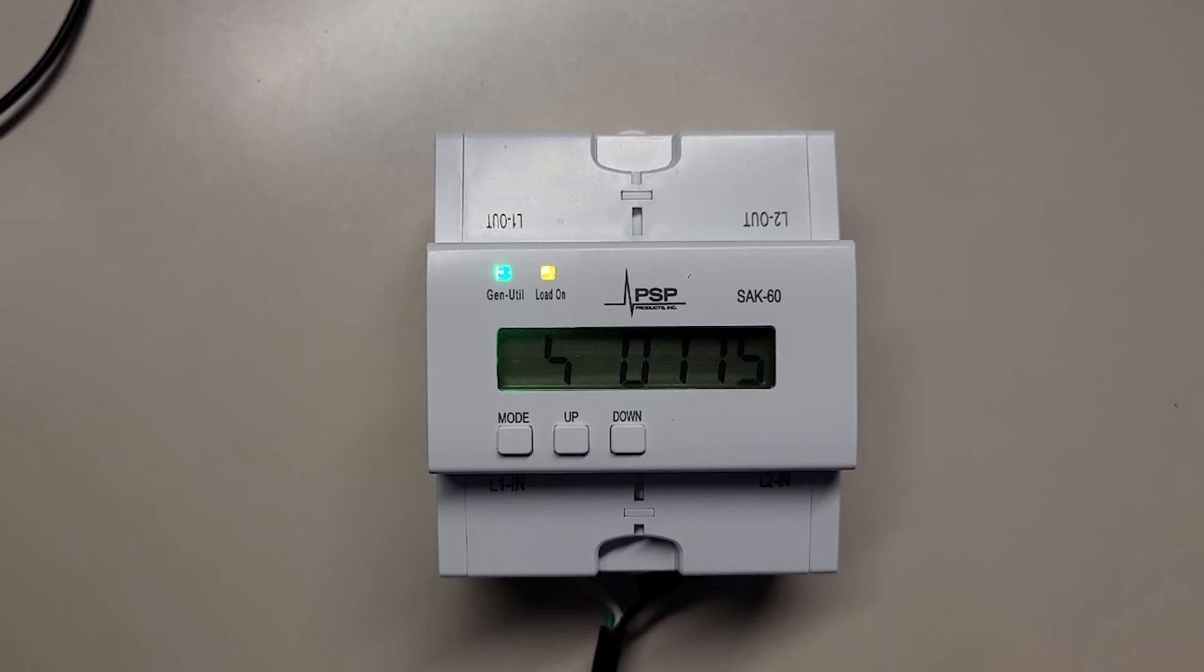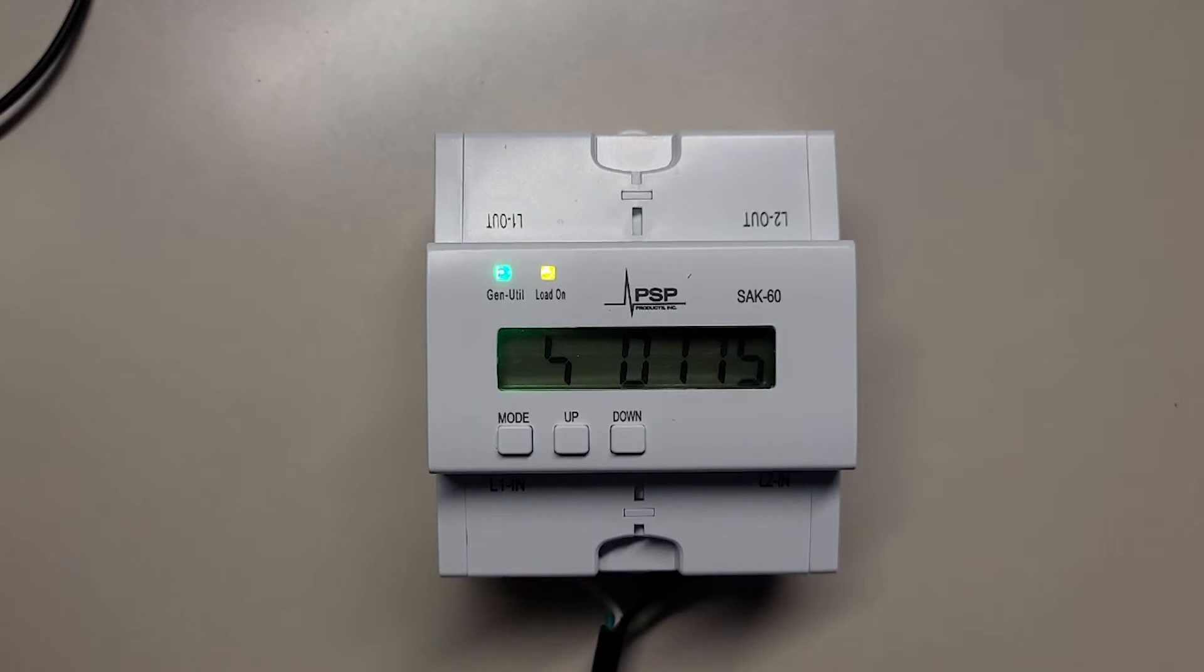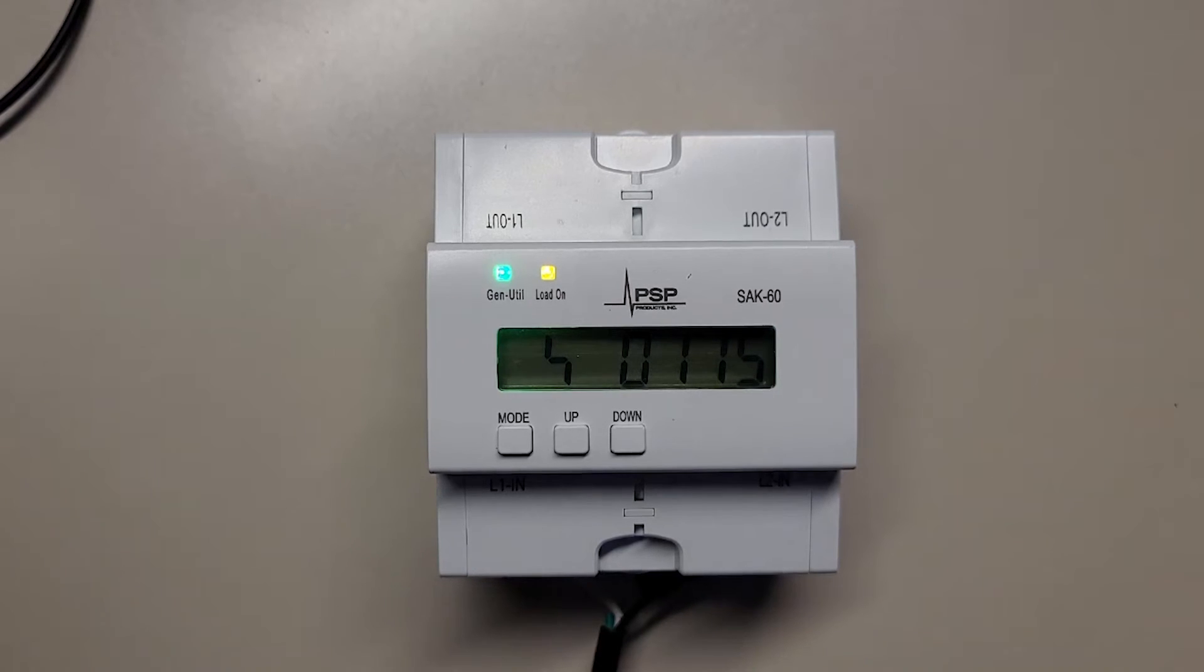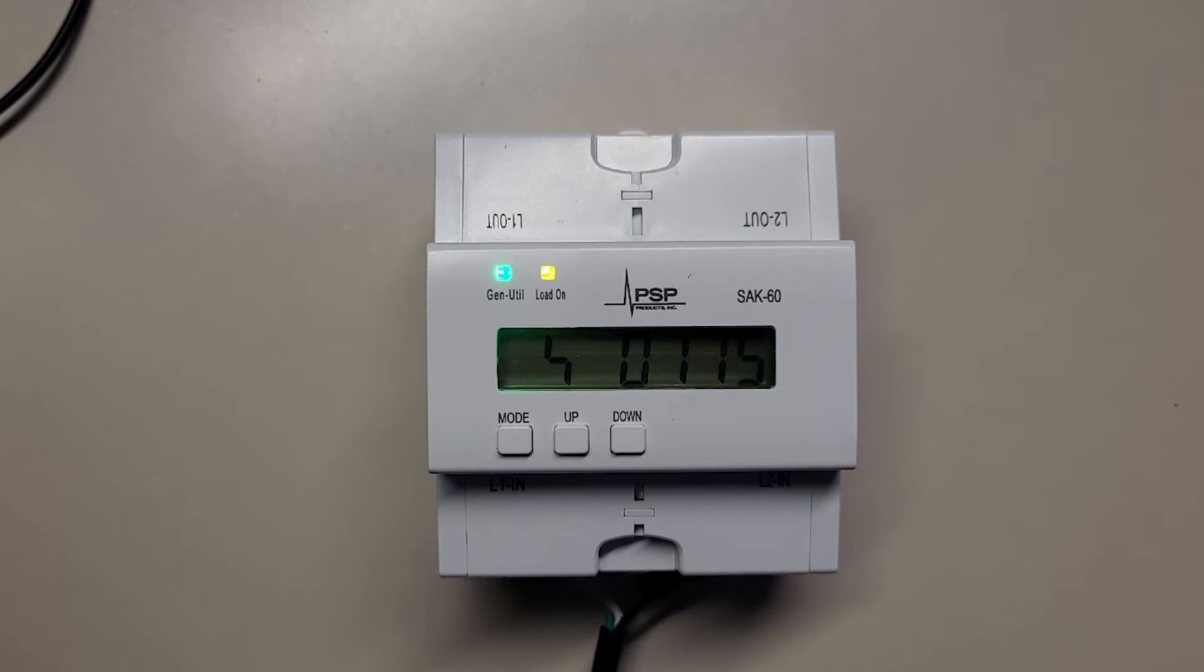The first application that we're going to consider is generator lockout. It's not uncommon to have a large load like a hot tub or double oven that the customer is okay with just locking out anytime they're on generator power. This is probably the easiest way to use the SAK and it doesn't require any connection back to the ATS.